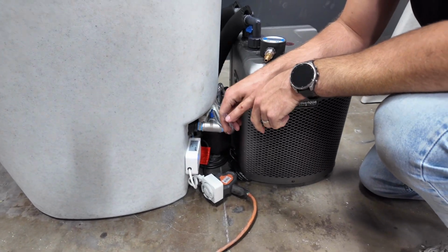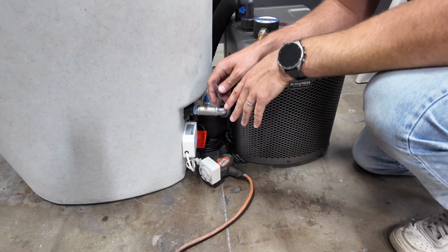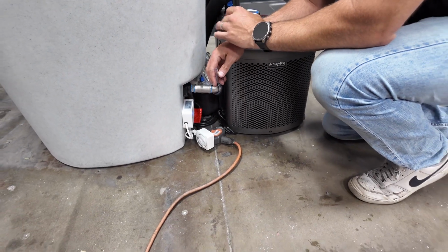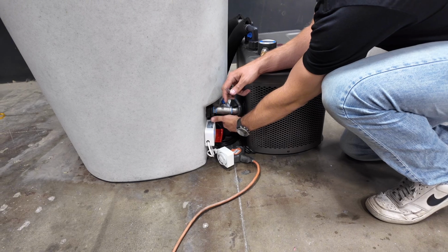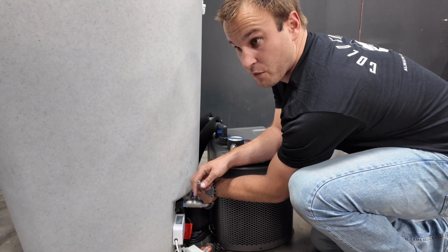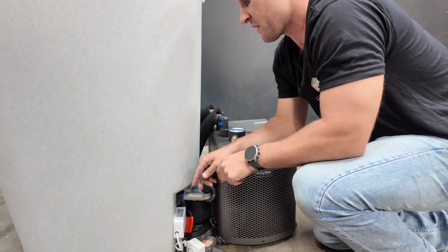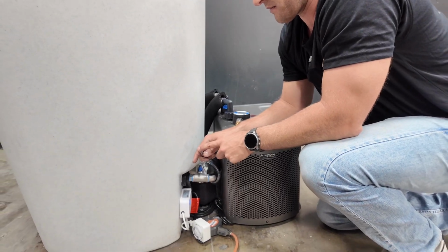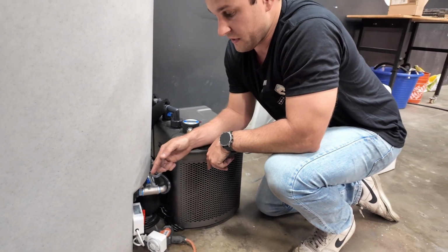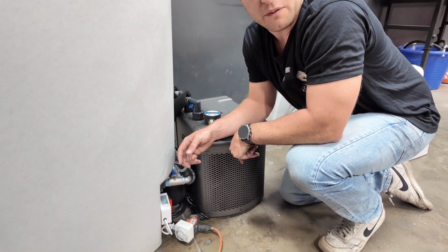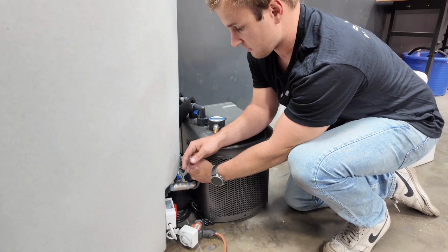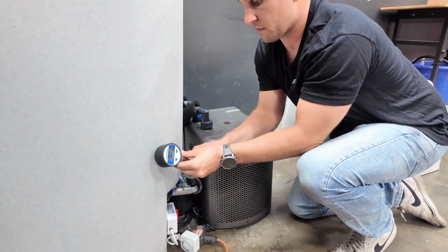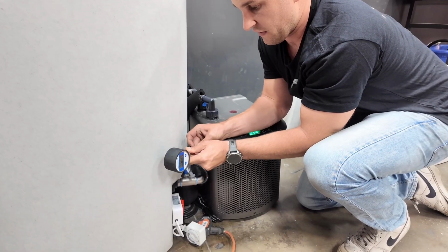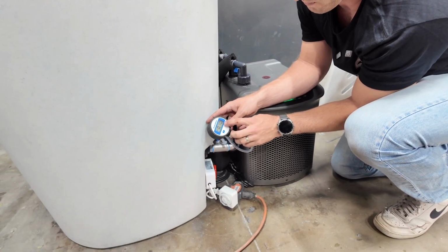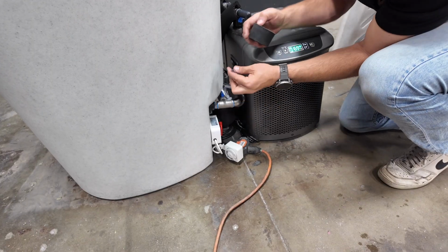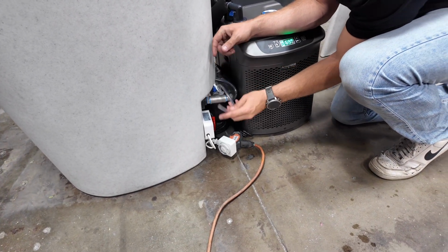But another cool test to show that the Venturi is actually working, because there are a lot of people that will install Venturis, but just not the right way. You need to have the back pressure of the water trying to go through the filter send water to the Venturi as well. It needs to create a vacuum. So if I put my finger over this hose, I can feel a vacuum, I can feel a suction. Even though it's connected here, there's no leak, because it's always just blowing in a suction. So we measured the vacuum. You don't need much. You can see it's just 0.1 PSI, and you only need enough pressure to open up that poppet valve so the ozone draws in.